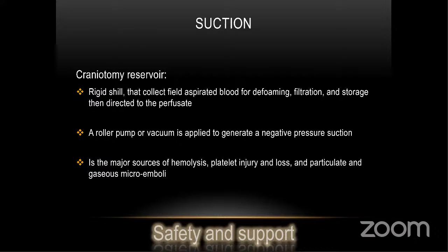A roller pump or vacuum is applied to generate negative pressure suction. And it is the major source, as we mentioned, of hemolysis, platelet injury and loss, and particularly gaseous microemboli.